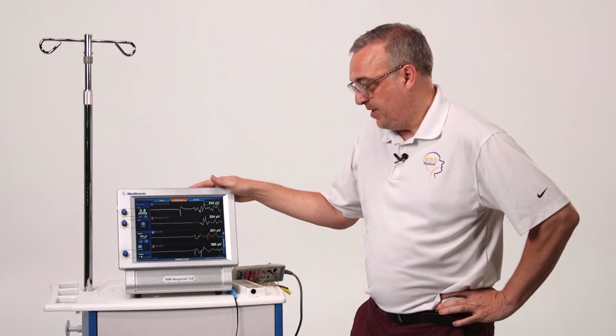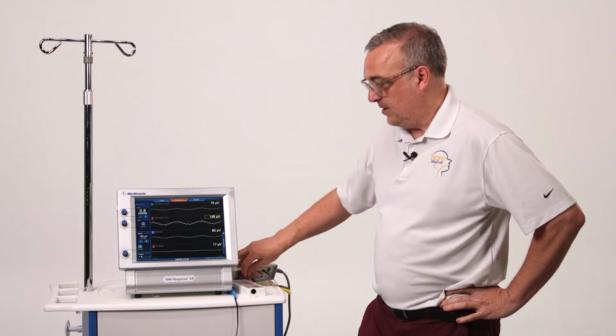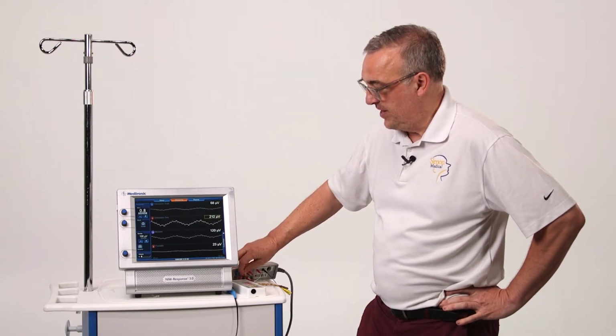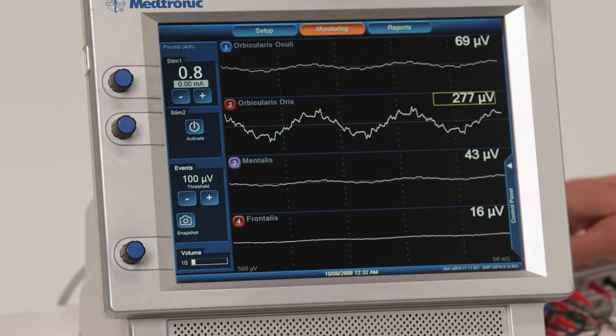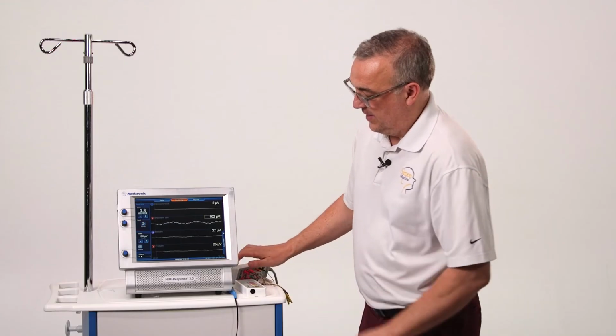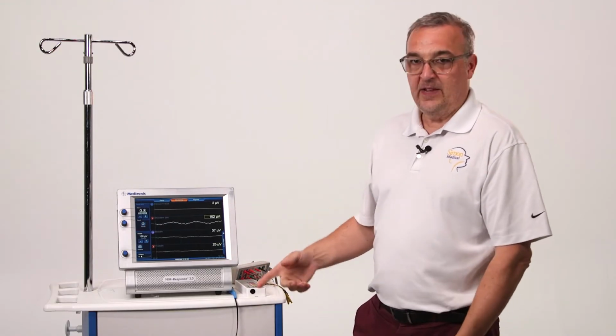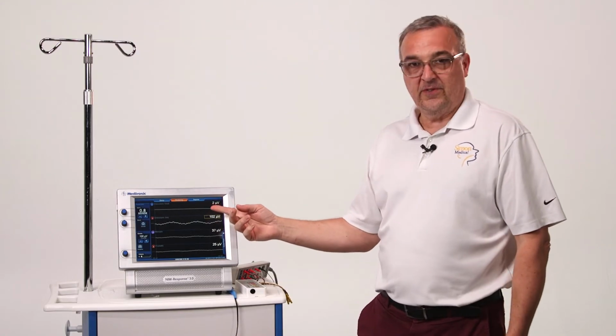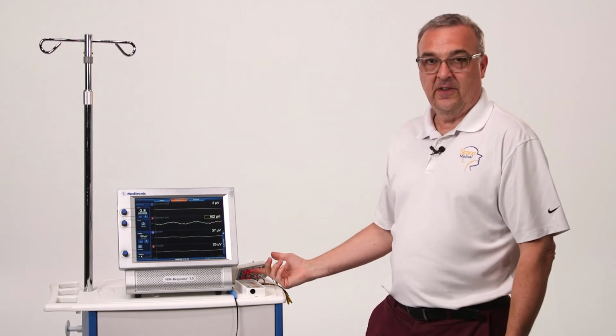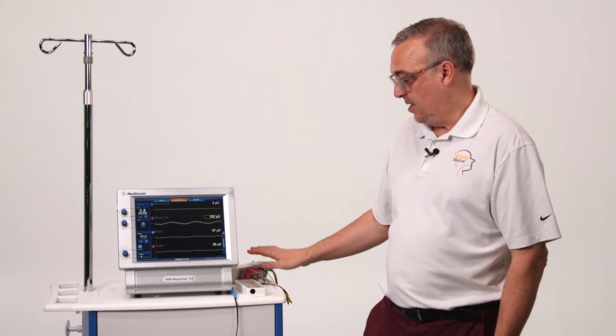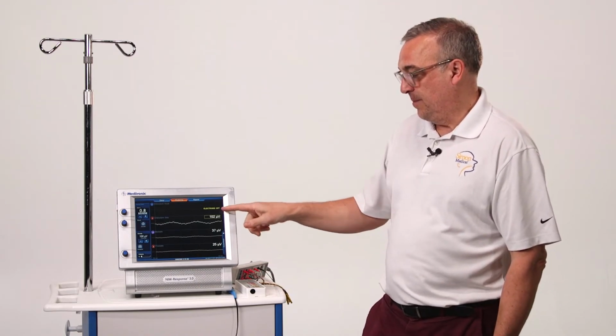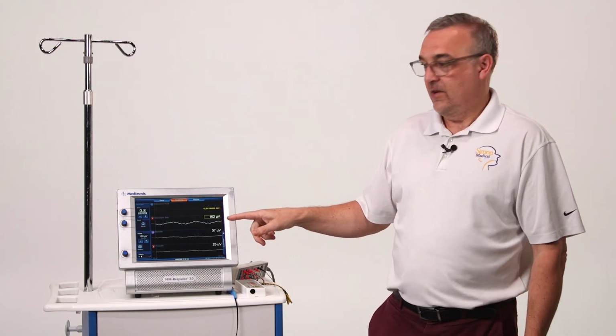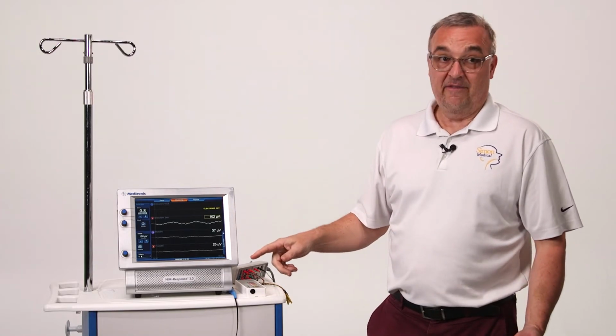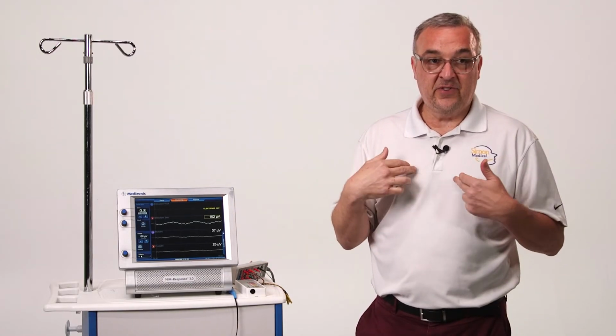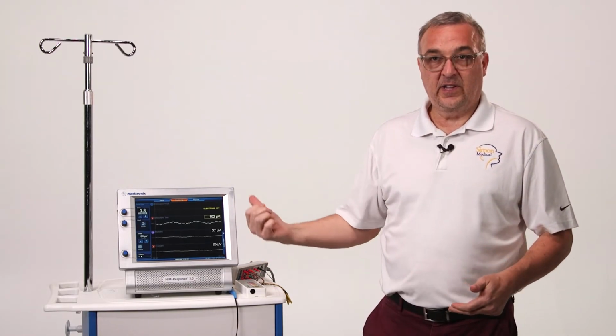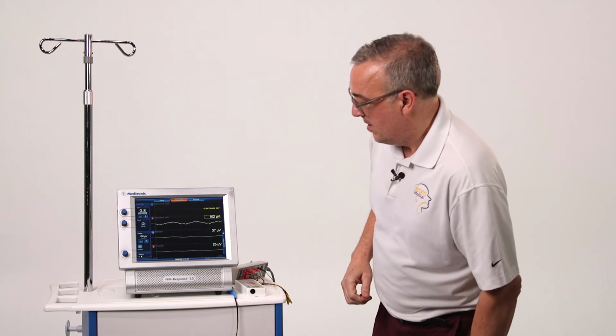From a troubleshooting point of view, if all of a sudden you lose a channel like this, you can go back and check the impedance. An electrode's come loose or it's come out of the box. So you need to go back and look at the box, and then run the impedance check. Or if an electrode's off, it's off. You need to either find it on the patient, or look in the box and see if it came out, okay?